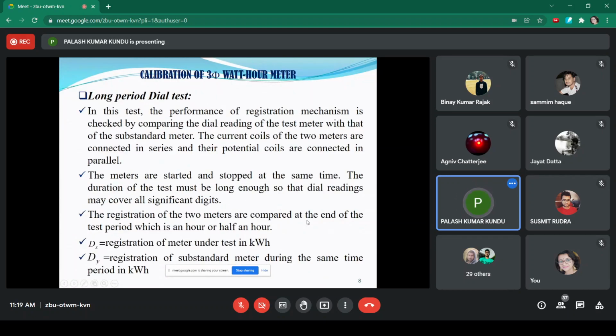Then there is another testing method, called the long period or the dial test. In this test, the performance of the registering mechanism is checked, in addition to the error caused by the disc rotation. As the disc is mechanically connected by the common shaft to the registration mechanism, definitely another error will cumulatively arise. So that error will be computed under the long period dial test.